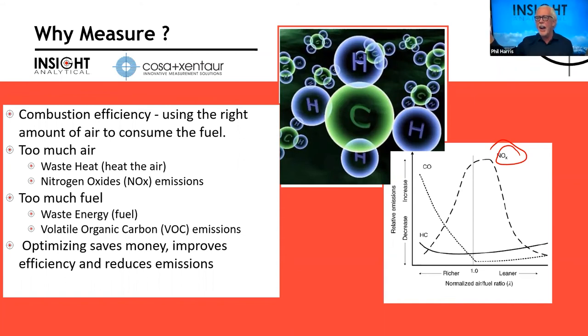For things like stack gas emissions, we often just measure the amount of excess oxygen that's going out in the stack. And as long as there's some excess O2 there, we say, well, we got a good burn and we probably burned all of the contaminants like sulfur or whatever. If it's a sulfur plant stack, we've burned what we wanted to in the stack.